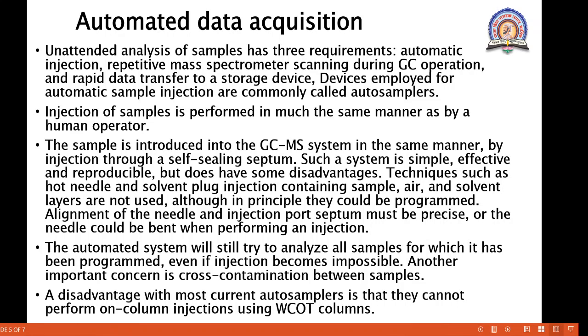Automated data acquisition: unattended analysis of samples has three requirements — automatic injection, repetitive mass spectrometer scanning during GC operation, and rapid data transfer to a storage device. Devices employed for automatic sample injection are commonly called auto samplers. Injection of a sample is performed in much the same manner as by a human operator.